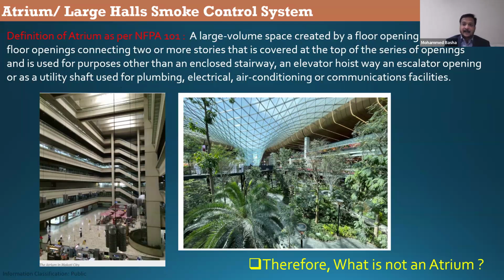So the focus here is the atrium, because it is the place where we need the smoke management system, because it is open to the smoke-generating space and we need to maintain tenable conditions for the occupants to go away. For example, if you have this building but it is all covered by glass, then this building is no longer referred to as an atrium. You do not need a smoke management system. Since the communicating space, that is the corridor, is open to the atrium, then we need to have a smoke control system.